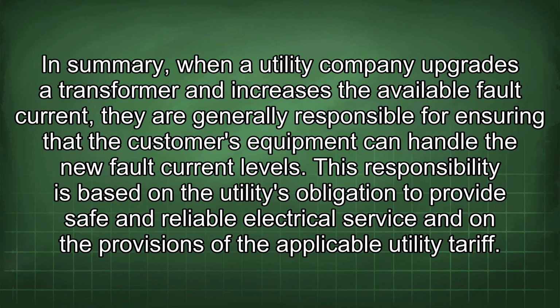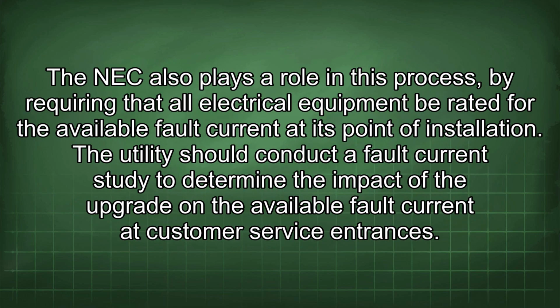This responsibility is based on the utility's obligation to provide safe and reliable electrical service and on the provisions of the applicable utility tariff. The NEC also plays a role in this process by requiring that all electrical equipment be rated for the available fault current at its point of installation.